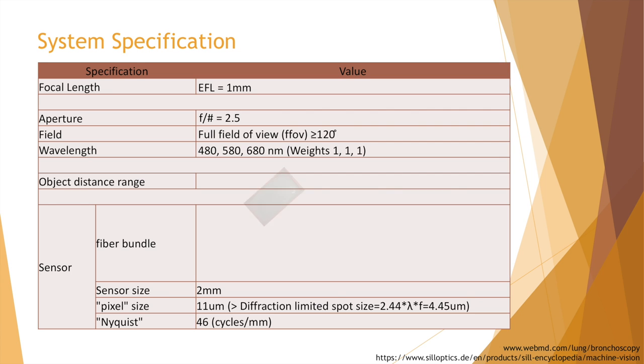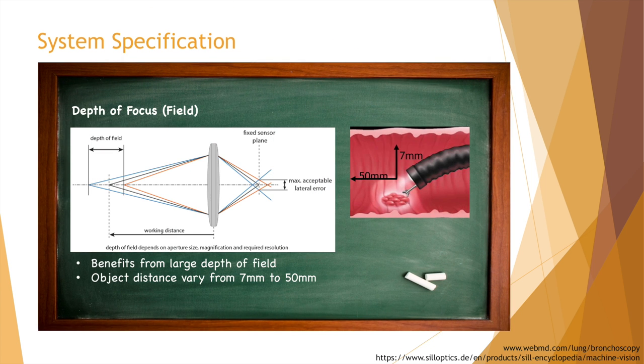To determine the object distance range, let's take a look at the depth of focus or depth of field. This refers to the longitudinal shift of the image sensor or the shift of the object that will produce an image degradation, but as long as the degradation is acceptable, the shift distance is within the depth of focus. Bronchoscopy benefits greatly from a large depth of field. The system needs to maintain high resolution even when the object is extremely close to the front surface of the lens. We push our target object distance from 7 mm, where biopsy can be successfully performed, to 50 mm, where normal detection distance usually is.